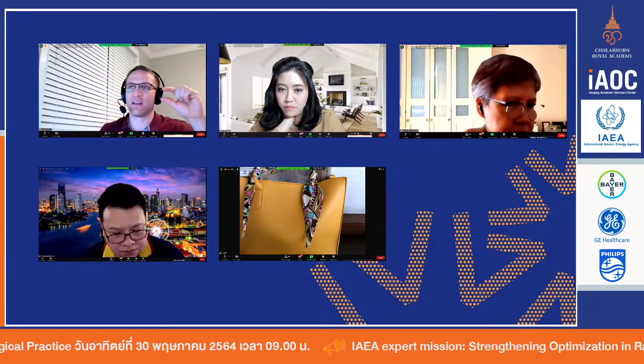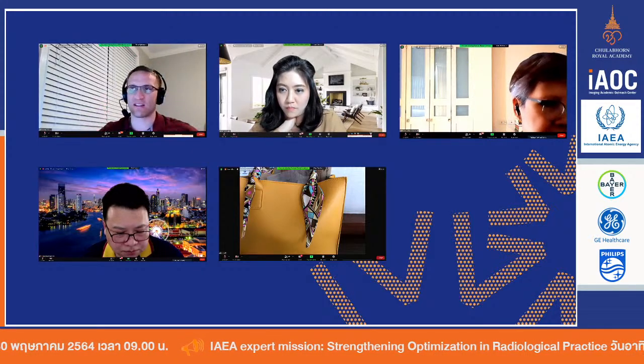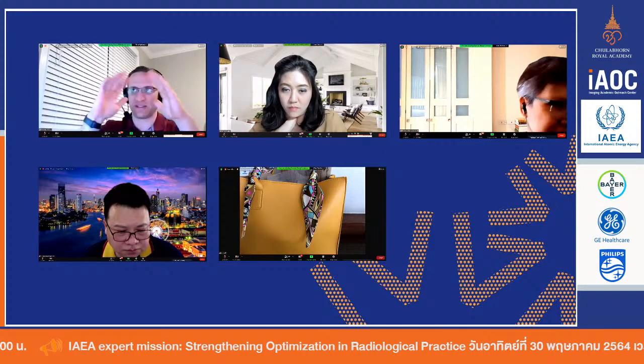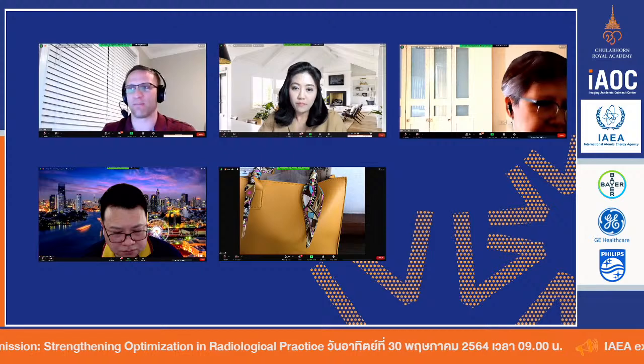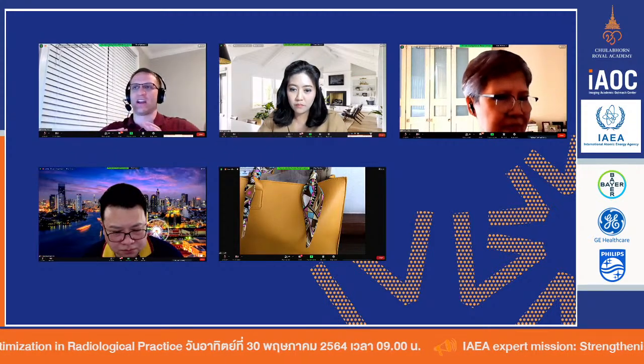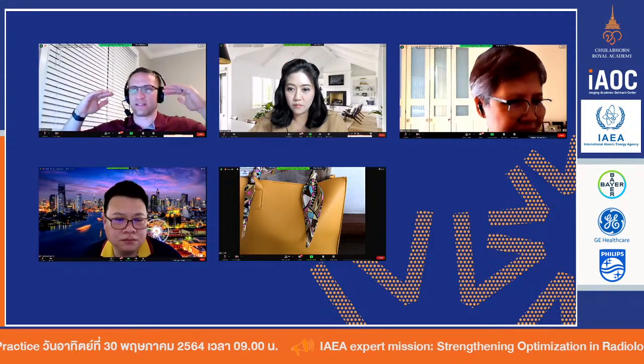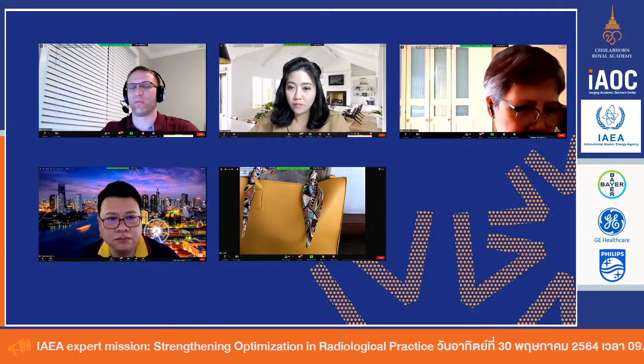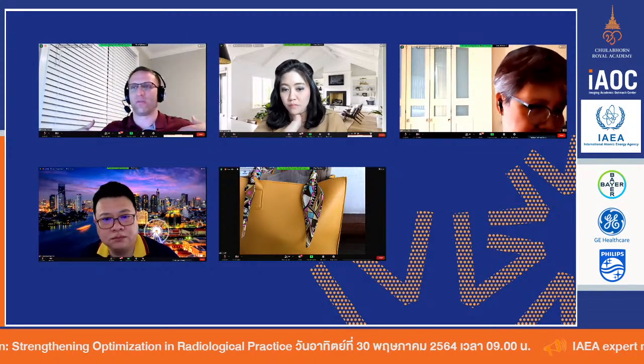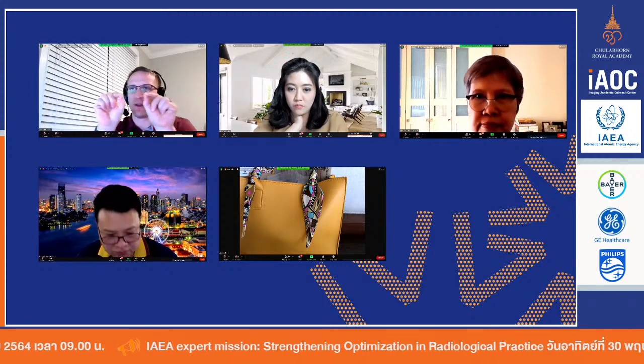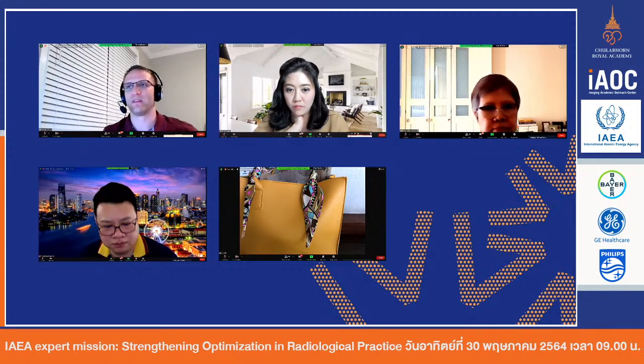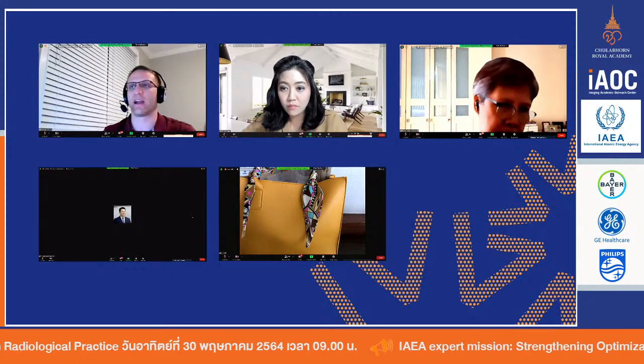So for the time being, if the software solution you choose does not receive a scout view or a planar radiograph from the CT, then it will be very hard, especially in the example that you provide. If you're doing a cardiac exam, you do a normal scout so you can localize the heart, but when you actually do the field of view, it's going to be truncated. The reality is you're irradiating all of the tissue around the heart. The whole chest is getting exposed, so the SSDE and the CTDIvol are still accurate to the full volume. It's just that if you make the measurement on the small field of view, your measurements would be wrong. So the software should be able to handle it accurately, and the software that you are using in Thailand will be accurate for that.